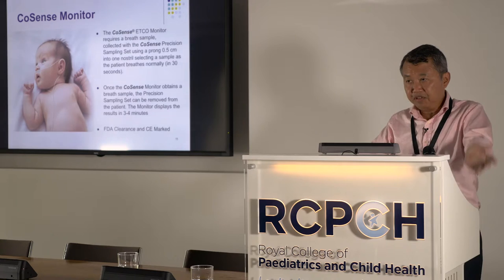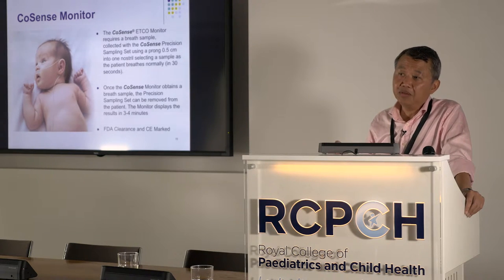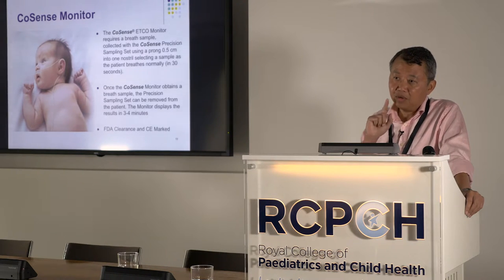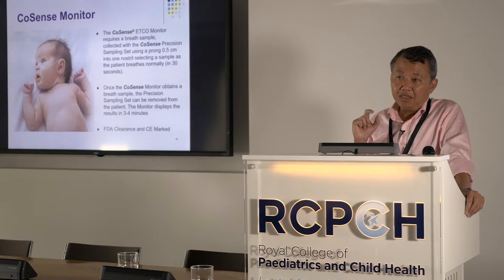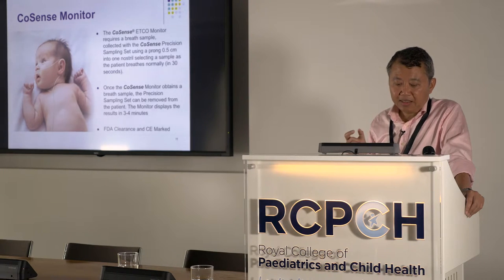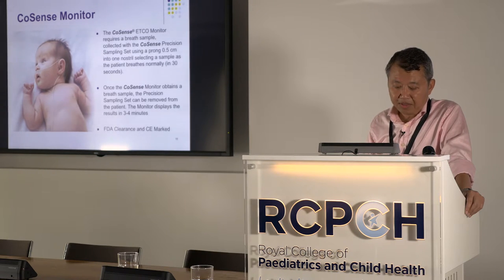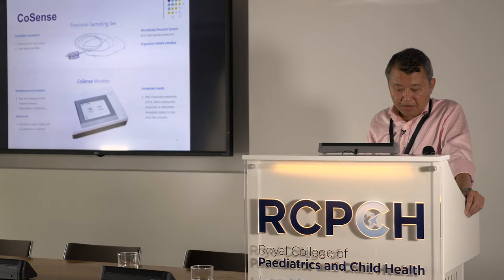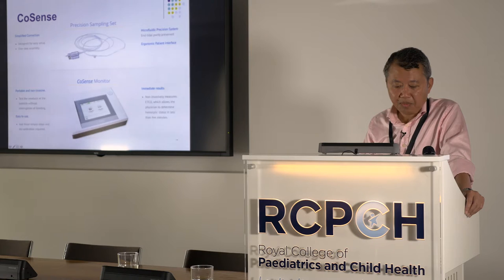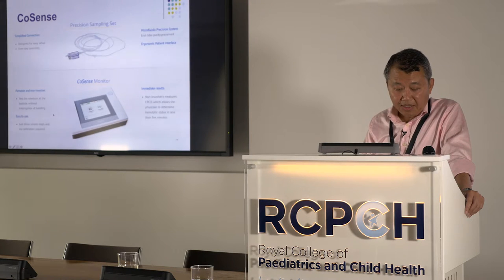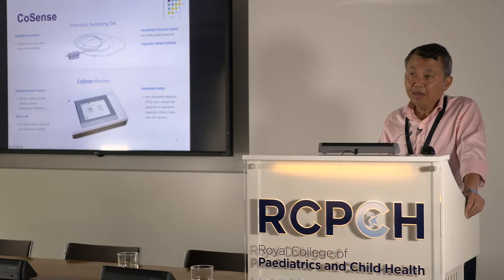You can see the device here. It measures a breath sample using a single prong that goes into one nostril and takes up to 30 seconds to detect a breath. After that, you remove the sampling set and the device shows the ETCO results in three to four minutes. It is FDA-approved and CE-marked. The sampling set attaches to the monitor at one end, and the prong is placed in one nostril of the baby — it's a one-step assembly, very non-invasive.